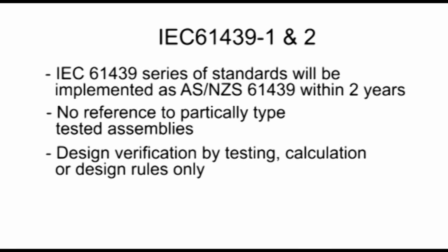There are significant changes to testing and results from testing. Some results and tests from the previous standard will still be valid. These are especially relevant for short circuit tests and through fault tests. Changes have been made, as one of our other speakers spoke about, in regards to temperature rise tests. Some other verification tests in the new standard are a lifting test, a corrosion test, and an impact test. I'll say it again, verification is the word.